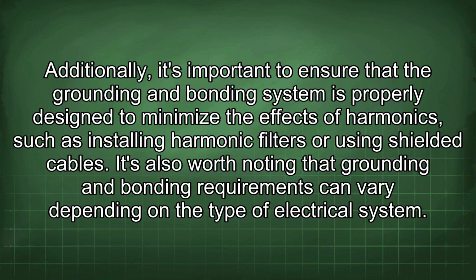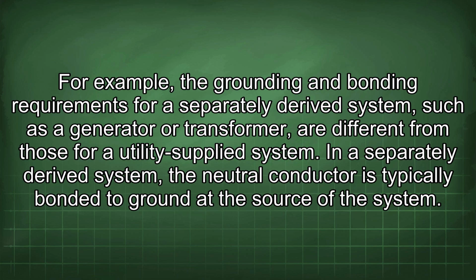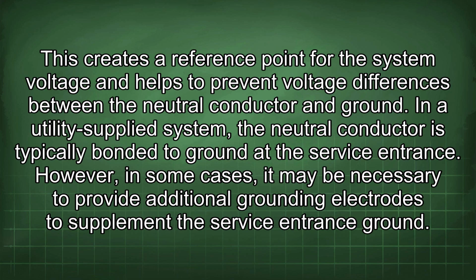It's also worth noting that grounding and bonding requirements can vary depending on the type of electrical system. For example, the grounding and bonding requirements for a separately derived system, such as a generator or transformer, are different from those for a utility-supplied system. In a separately derived system, the neutral conductor is typically bonded to ground at the source of the system. This creates a reference point for the system voltage and helps to prevent voltage differences between the neutral conductor and ground. In a utility-supplied system, the neutral conductor is typically bonded to ground at the service entrance.